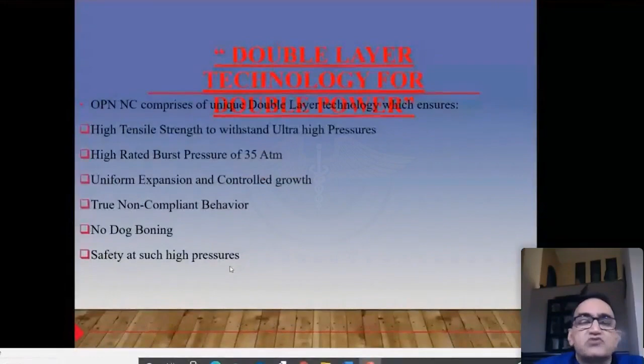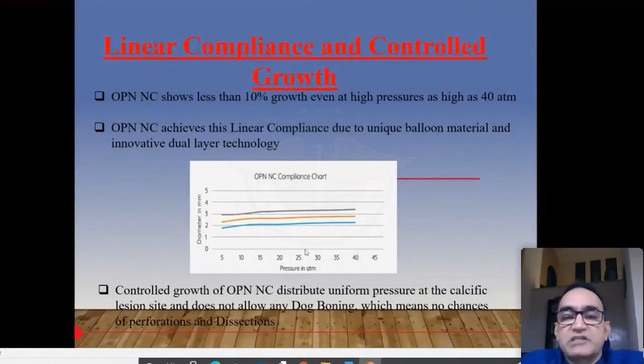Initially, people were not willing to believe that coronary arteries can withstand such high pressures, but experience has proven that they do withstand this high pressure. OPN NC shows less than 10% growth even at pressures as high as 40 atmospheres. OPN NC achieves this linear compliance due to its unique balloon material and innovative dual layer technology. You can see here, even when the pressures have gone up to 40, the diameter increase is relatively minimal.